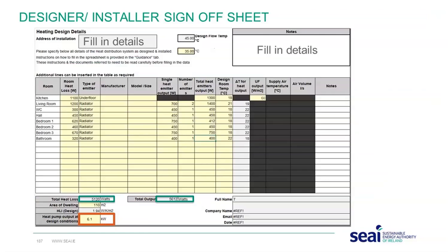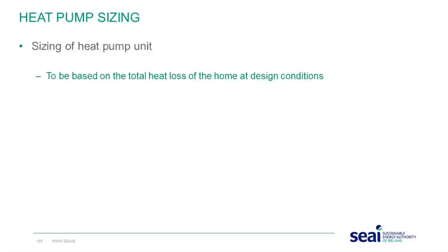Finally, then, this is an example of a completed designer installer sign-off sheet. We've all the radiators listed. We have the top one there in the kitchen. We can see it's underfloor heating. Key points to it, look, the total heat loss is 5,120 watts. The output of the radiator exceeds the heat loss in each room, which obviously is necessary, plus the output of the heat pump is greater than the total heat loss as well. So these things are very important, especially when we have to demonstrate efficiencies and compliance.